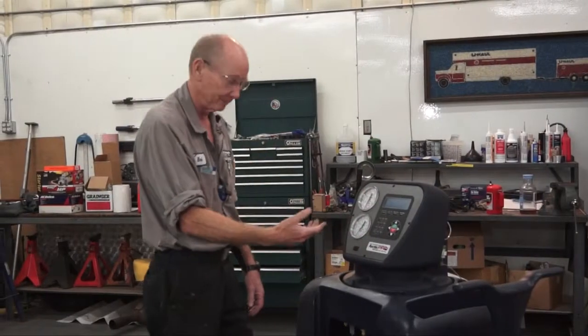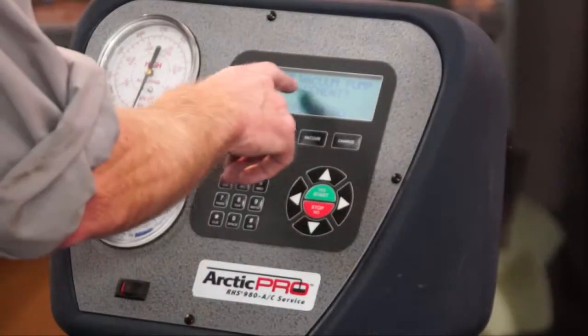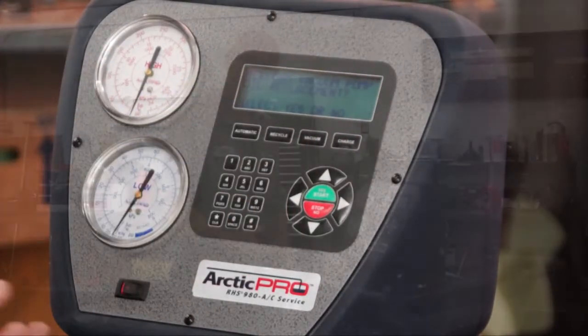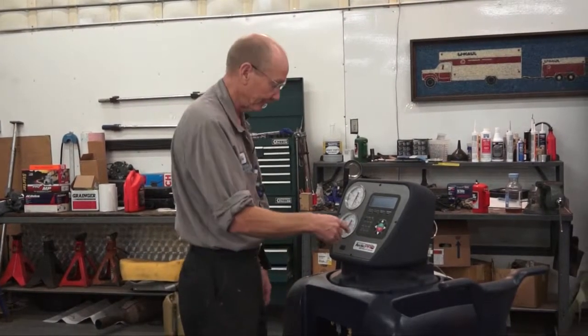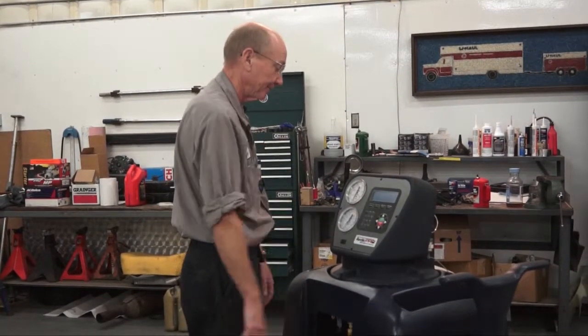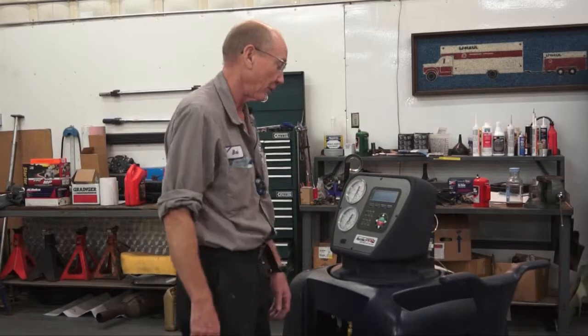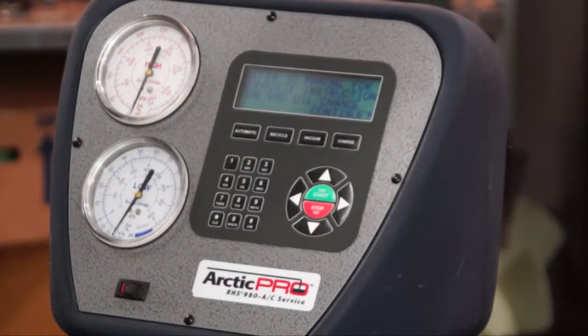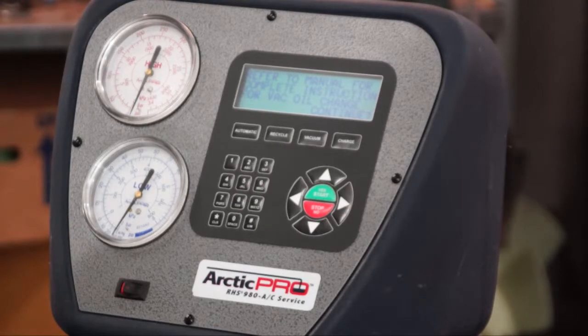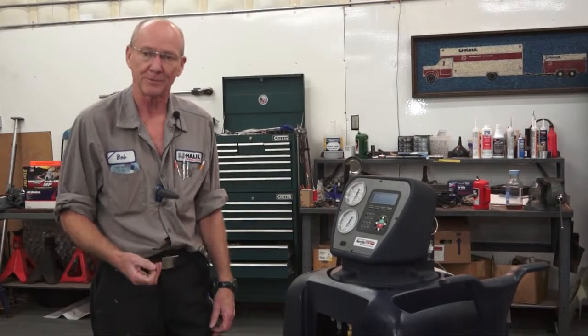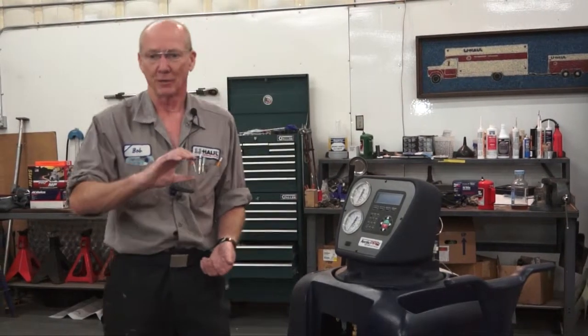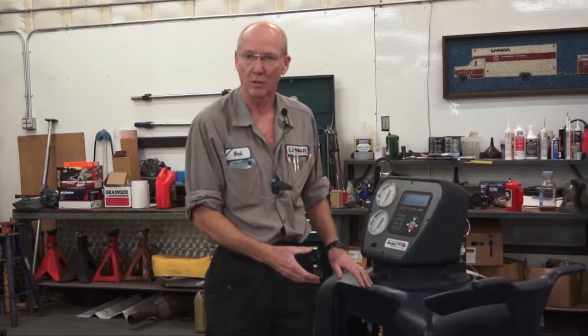Now I continue on. With the down arrow, I'm going to get to perform vacuum pump oil replacement. I'm going to hit yes, because that's what I want to do. Now that we've calibrated the machine, hit yes. That's telling me to refer to the manual for complete instructions for a vacuum oil change. Again, the manual will only give you a certain amount of instructions. It's just not a matter of draining it. There's certain steps you have to do. You just can't drain it, fill it back to capacity, and turn the machine on. Again, this vacuum pump is already warmed up, and the oil will drain out quicker. So it's really good to do that right after service so you don't forget.